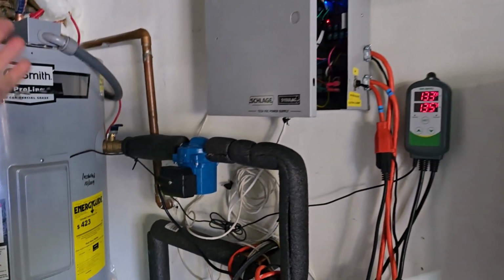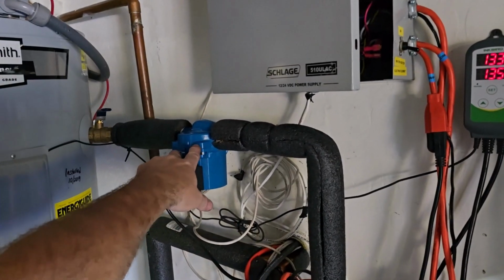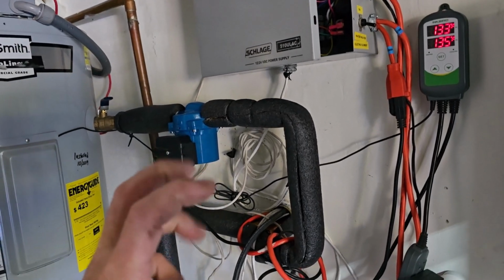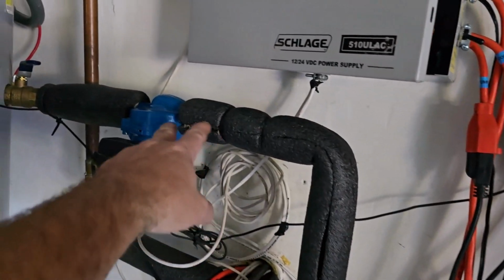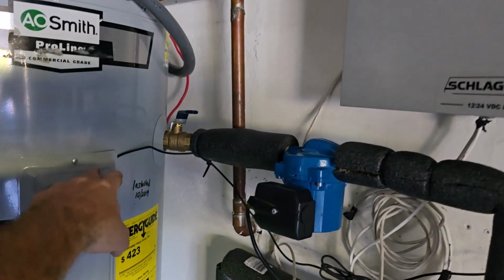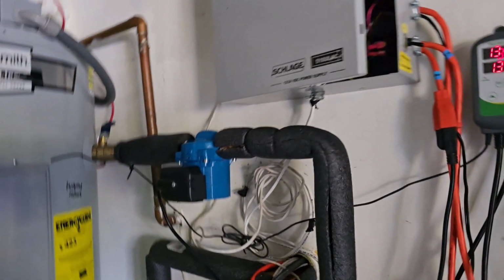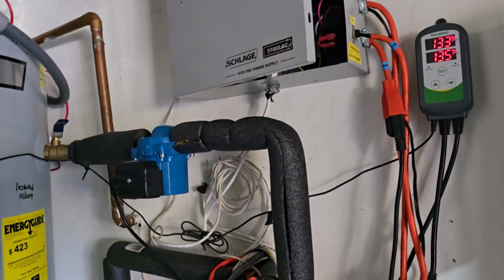And I do a 2-stage pump. The liquid line has to get up to over 100 degrees before it even starts to pump on low speed. That way I get a heat rise all the time from that cold water, which comes in below, goes through that heat exchanger outside, and then goes back into the top. The sensor's just in here. Running this off of liquid line temp has been working excellent.